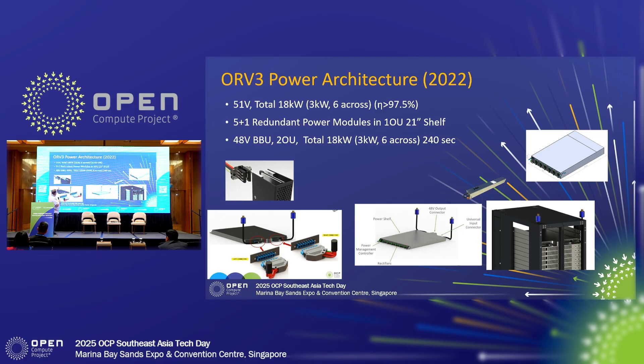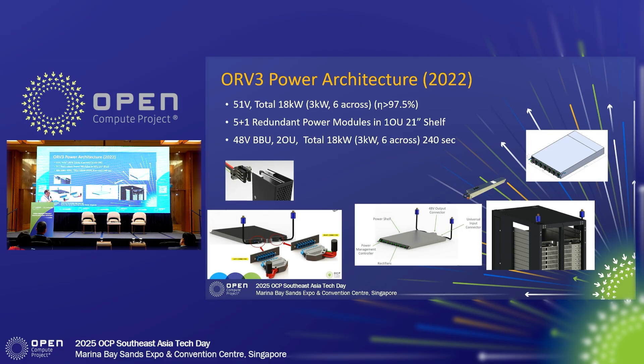So in ORV3 the bus bar is like a PC board with metal on both sides. What's nice about that is there are no holes, nuts, or bolts — you can just slide the server in anywhere you want along the way. We also created a six-across power supply: six of them at 3 kilowatts each, giving you 18 kilowatts that you can slide in wherever you like. The big thing was reducing current by increasing voltage — going to 54 volts, or 48 volts, or 51 volts. When somebody says 48 volts, it could actually be 54 or 51 — don't be confused.